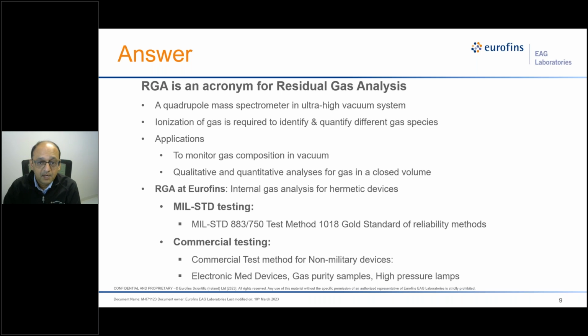For example, when we are doing medical devices, the device may be at a temperature of 40 degrees Celsius, closer to the body temperature, which is a deviation from the MIL standard. Because in MIL standard, the entire testing is done at 100 degrees Celsius. The sample is at 100 degrees Celsius. The mass spectrometer system, the vacuum system, the entire chamber is at 100 degrees Celsius, and we cannot deviate from that. But when we do medical devices with some kind of an exception, then that will be termed commercial testing. So RGA in general is a gas measurement system, and it can be developed into a very specific kind of test measurement system. But the core of the RGA system is a quadrupole mass spec system working in ultra-high vacuum. So I think that would give a little bit of an idea on what RGA is in general.